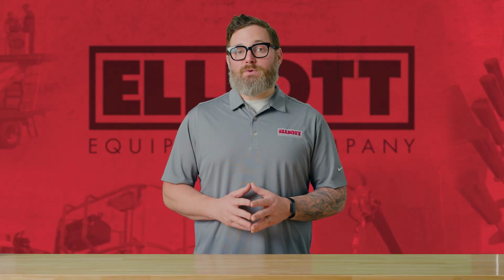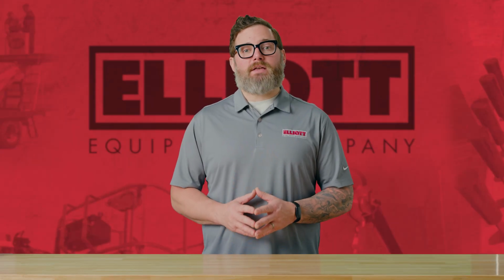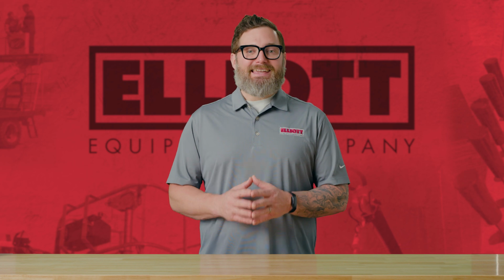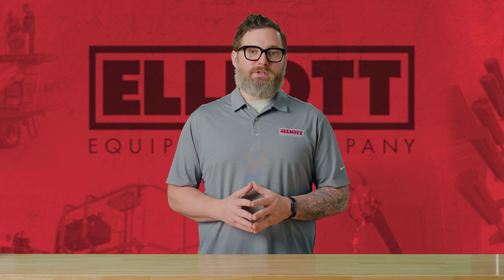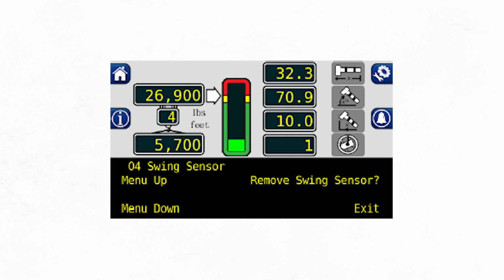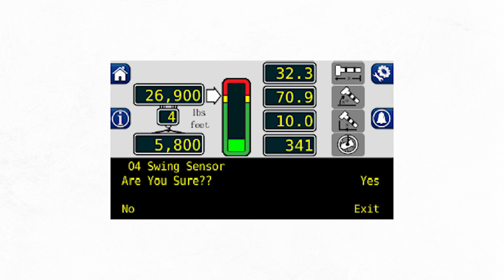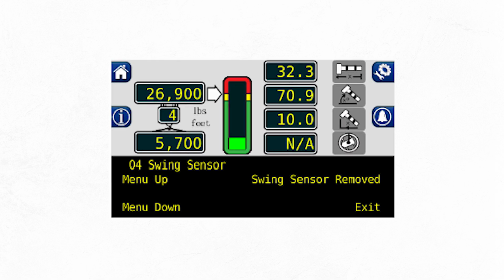Now, Elliott does not utilize the swing sensor, so it may be necessary to disable the functionality in the calibration menu. To do this, enter the calibration menu and press Menu Up to display 04 swing sensor and press that button. Then press the Menu Up button to display the Remove Swing Sensor option and press that button. When you are prompted with an "Are you sure?" press the Yes button. The swing sensor is now disabled and the swing angle window will display Not Available instead of a number.